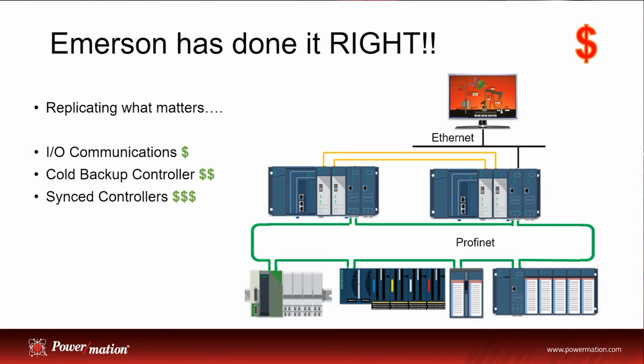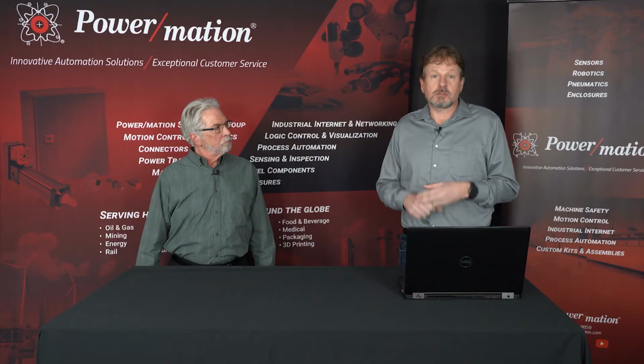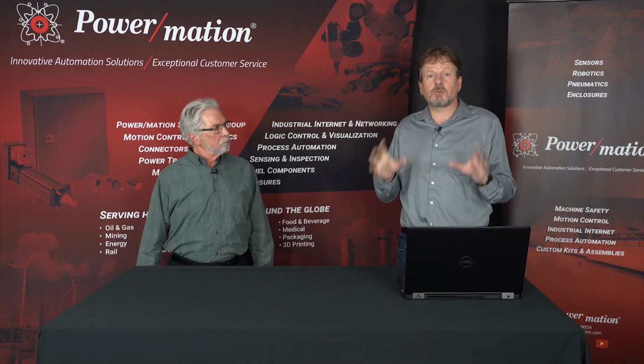So what we have the ability to do is take these two controllers, sit them side by side, and with a fiber optic link between them, we can synchronize the scans and we can synchronize all the I/O. So now both of these controllers are primed and ready to go.